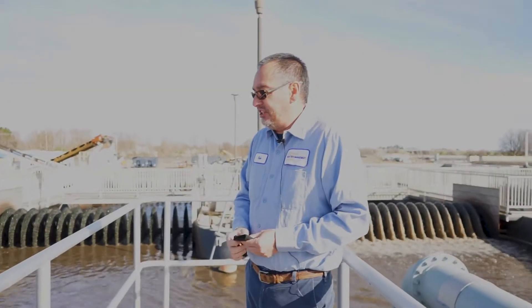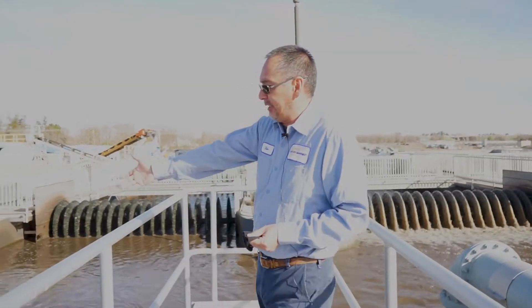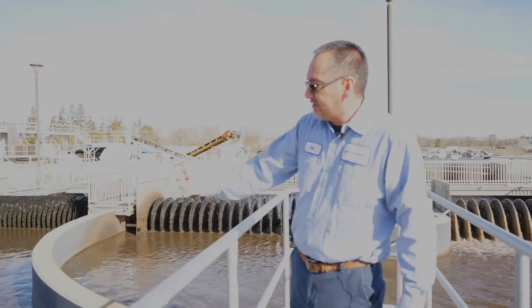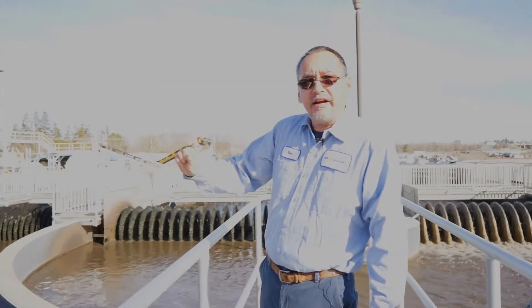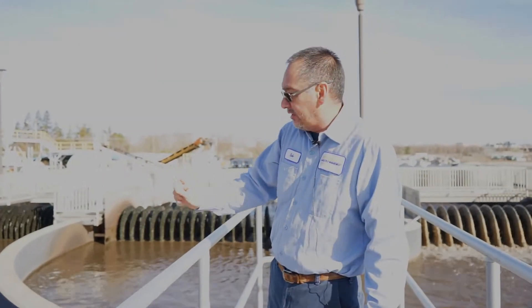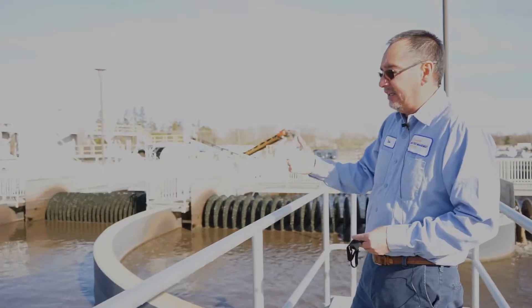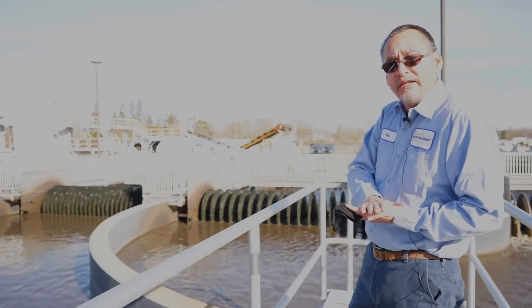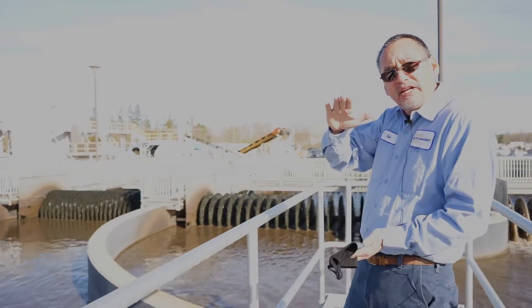We're up on the oxidation ditch. As you'll see, the mixed liquor is a brownish color. We have a nice clean layer, about an inch on top. You'll see these nice dark lines in the mixed liquor — this is what we call flocculation. When we see this, we know it's healthy, and the mixed liquor will settle in the next process of clarification. It'll give us that nice fine separation.